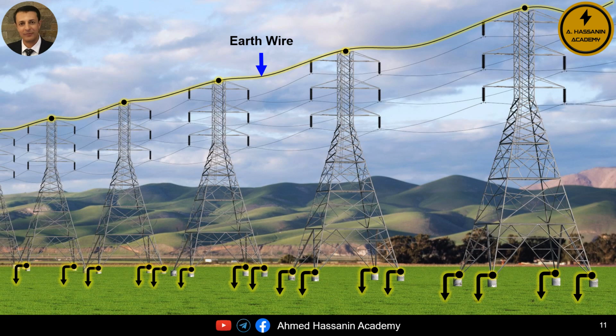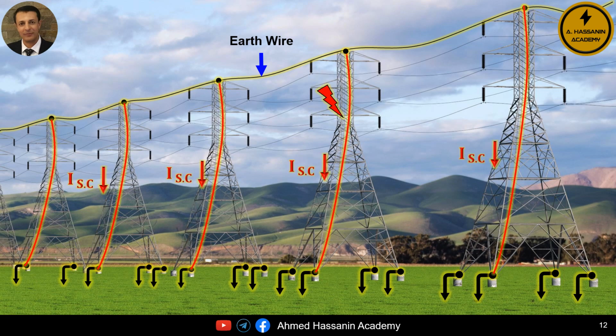The third thing is that all the towers are grounded from the bottom. We all know that the earth itself acts as a conductor, so we understand from this that all the towers are connected to each other from below through the grounding and the earth. Consequently, we understand that the earth at the bottom and the earth conductor, shield wire or earth wire or ground wire at the top make all the transmission line towers connected in parallel with each other. Of course, as I mentioned earlier, the lightning current or earth fault currents are discharged to the earth through the metallic structure of the tower. Therefore, the paths for these currents are the metallic tower structure itself.